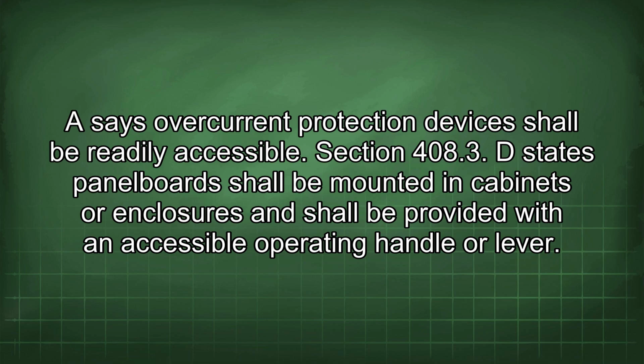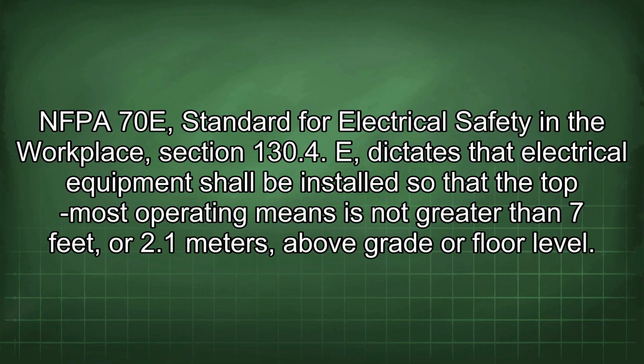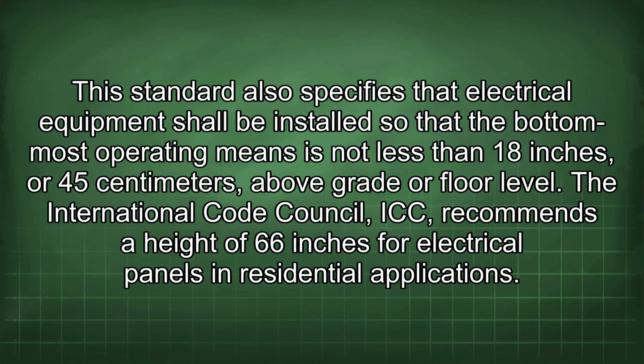handle or lever. NFPA 70E Standard for Electrical Safety in the Workplace, Section 130.4 dictates that the electrical equipment shall be installed so that the topmost operating means is not greater than 7 feet or 2.1 meters above grade or floor level. This standard also specifies that electrical equipment shall be installed so that the bottommost operating means is not less than 18 inches or 45 centimeters above grade or floor level.